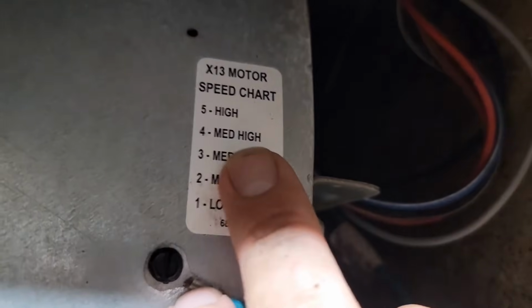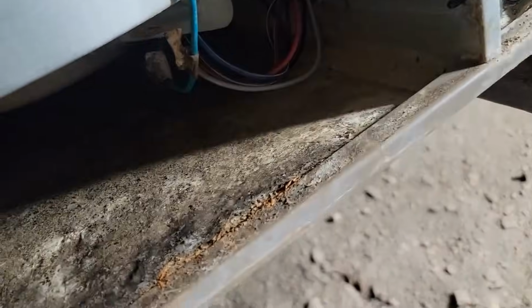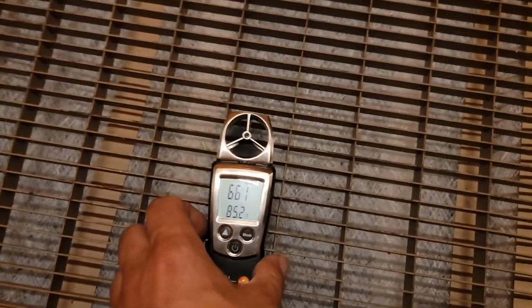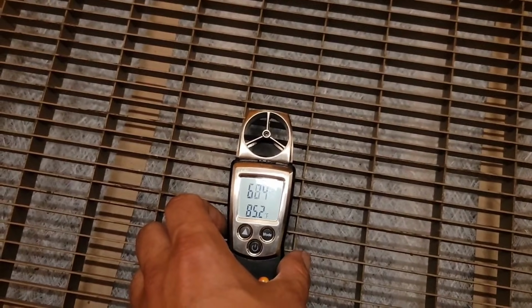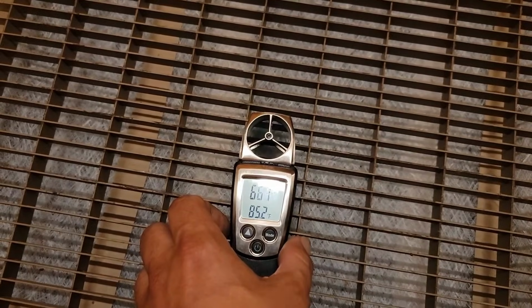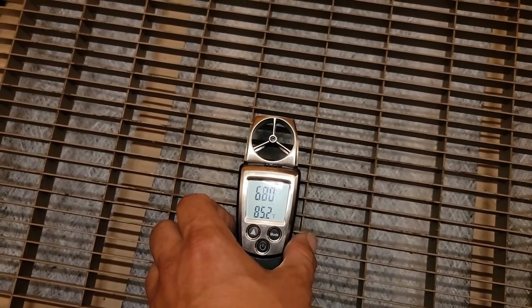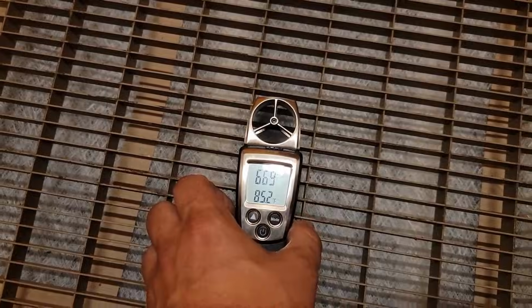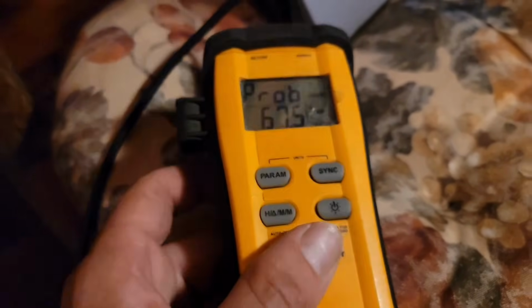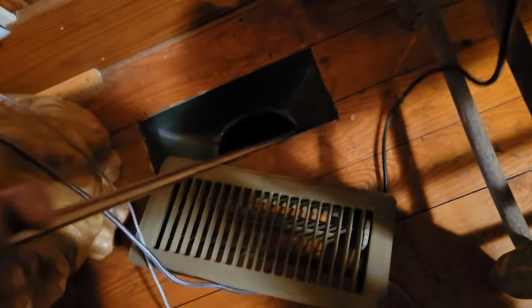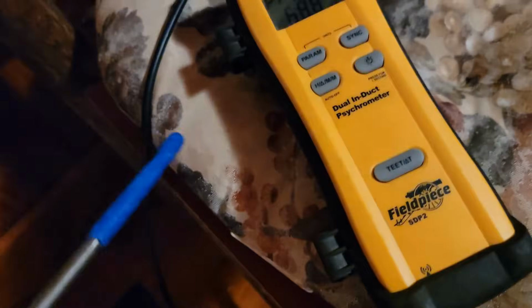All right, I just took the speed from medium high to medium. It was pretty easy. Now I'm gonna put the panel back on. All right, now let's see what we got. Well, it's a little lower. Not quite 750. Still 700 though, it looks like. Temperature coming out of the vent now is 67 degrees, so we are in good shape. Beautiful. That's the little probe there.